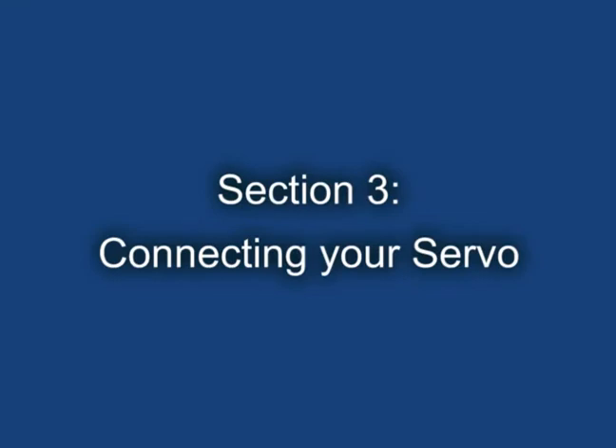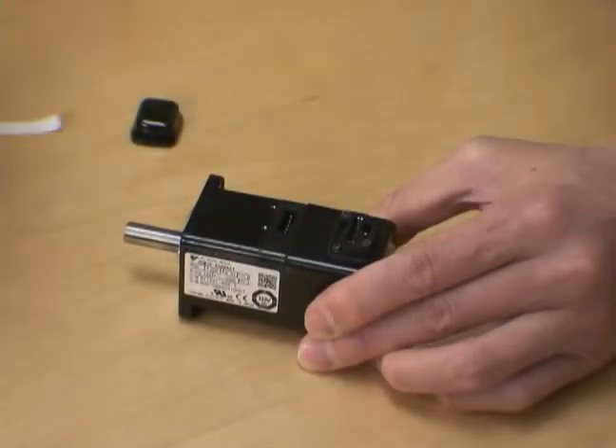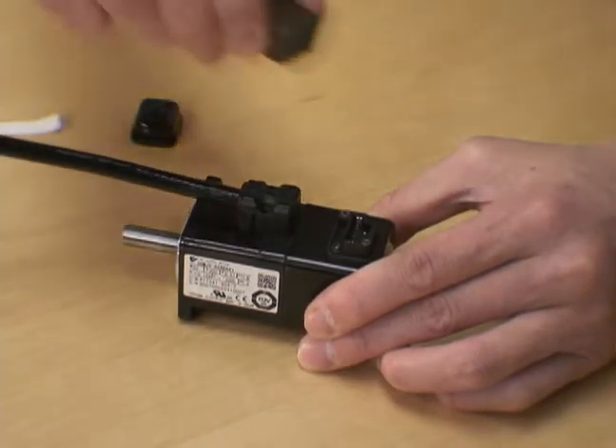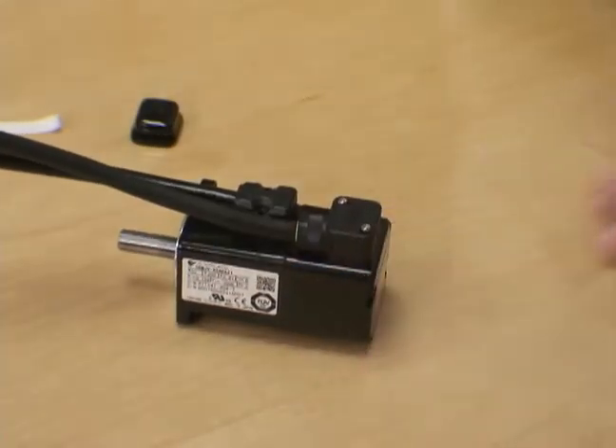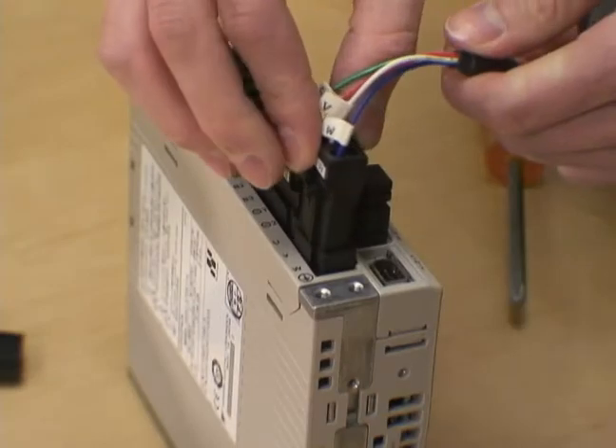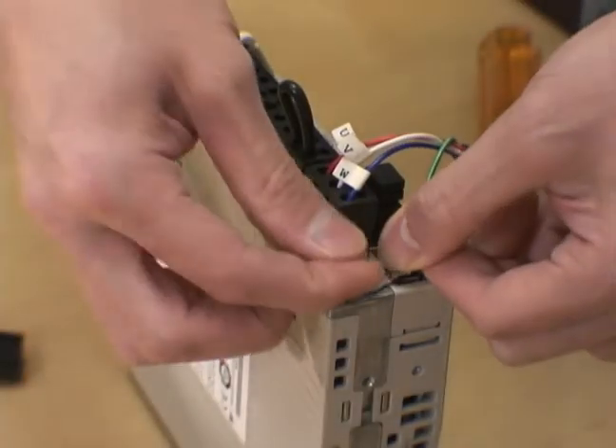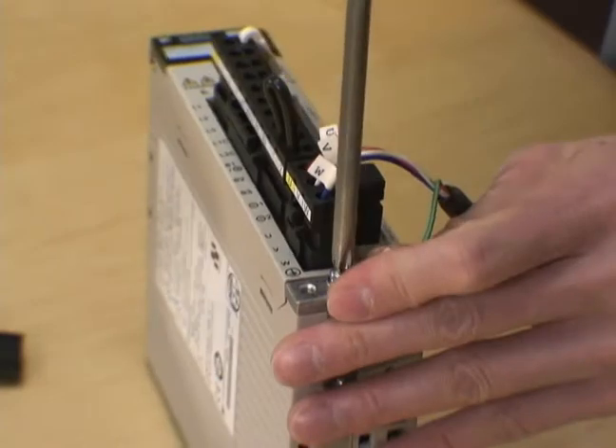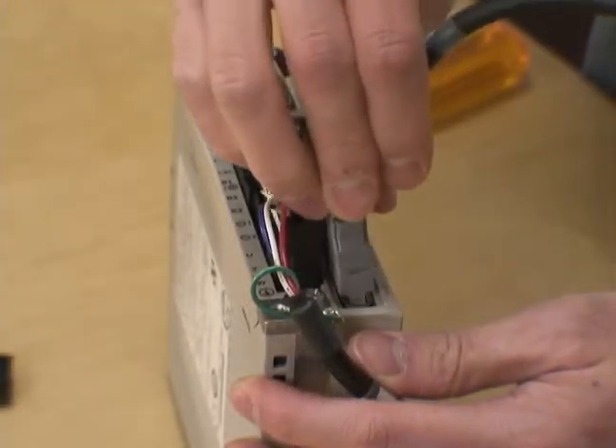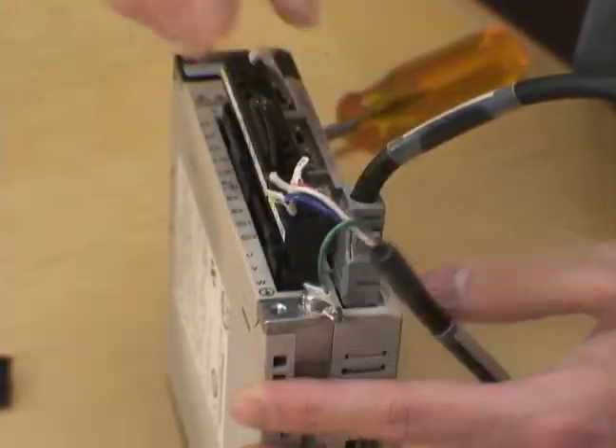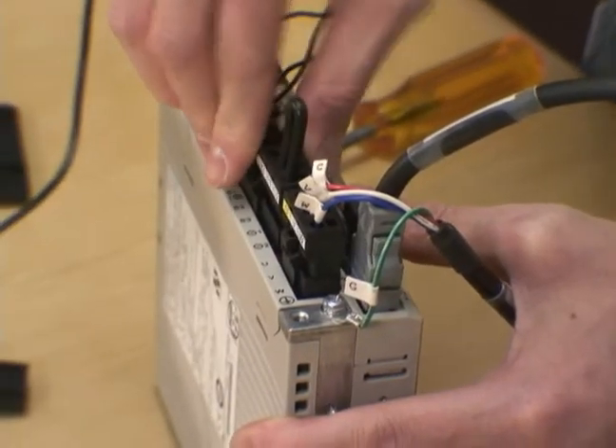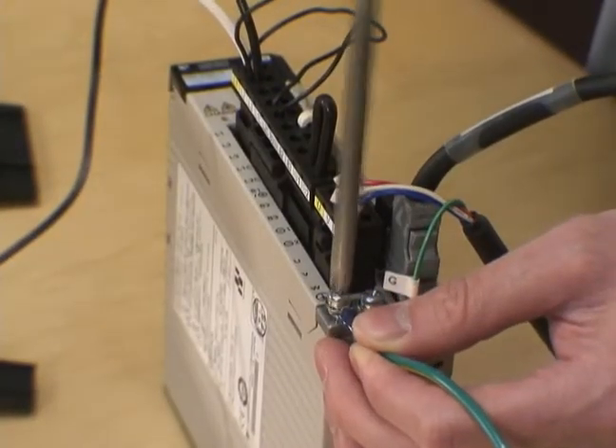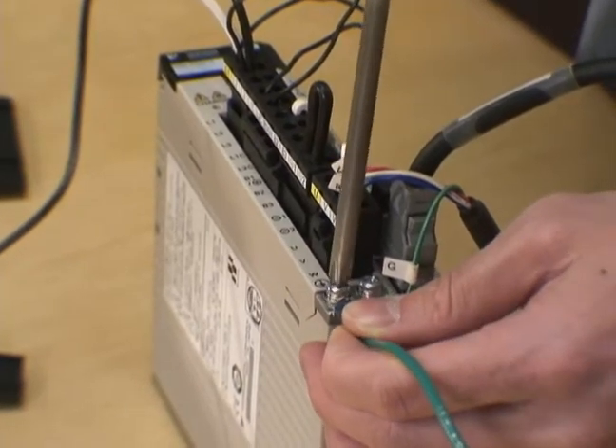Section 3. Connecting your servo. Put the motor power cable into the servo motor. Put the motor encoder cable into the servo motor. Put the motor power cable into the amplifier and screw down the ground wire. Connect the motor encoder cable to the amplifier. And wire the input power into the amplifier. Then screw down the input power's ground onto the amplifier.